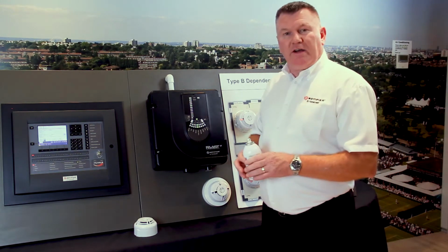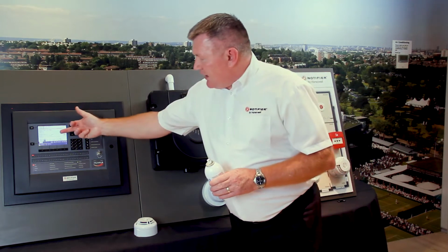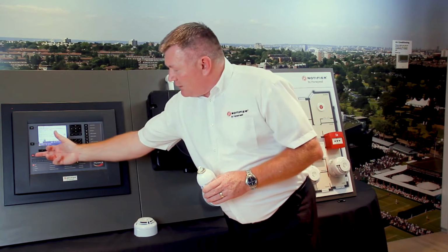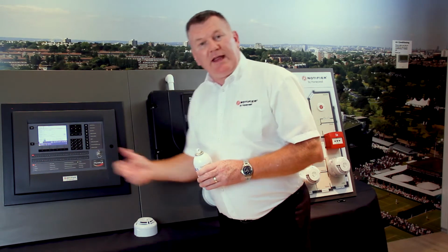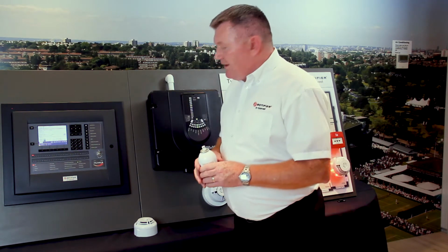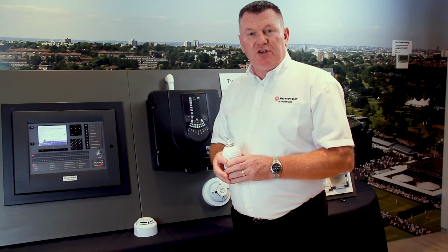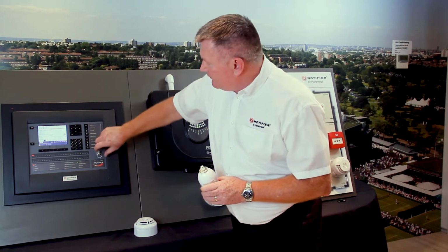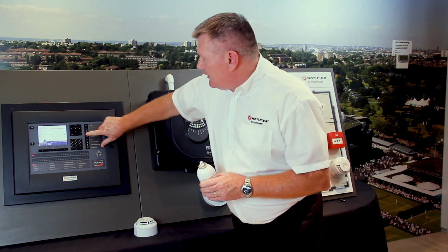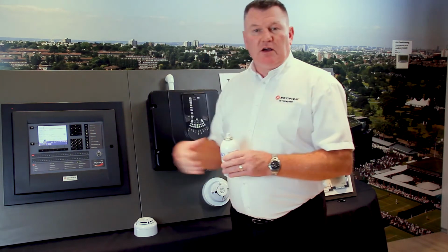We move across to the fire alarm panel. You'll see that the same zone is in alarm condition, so it tells us zone 1 is in alarm condition, but it also now lights the fire light. With this, we now have to do a manual reset of the fire alarm system. So we silence the system, we have to enable it, and we do a silence. That will silence the sounder.